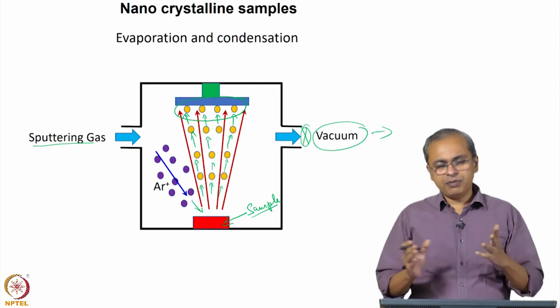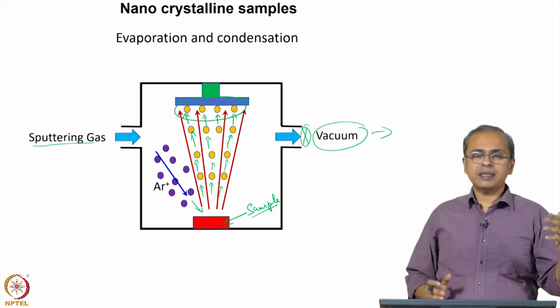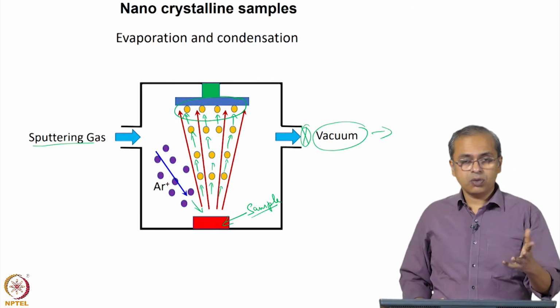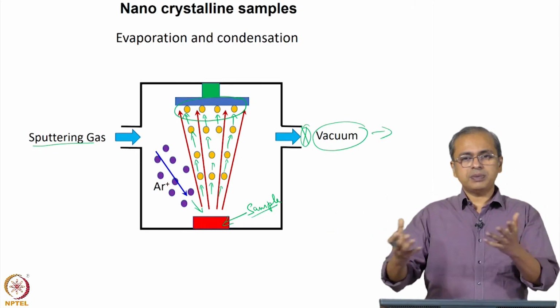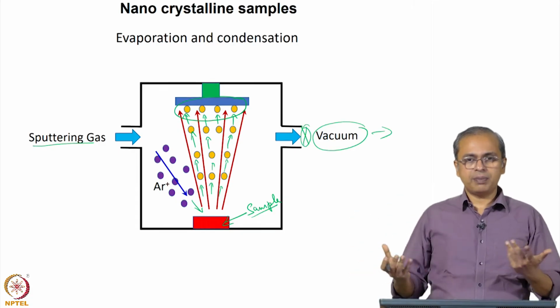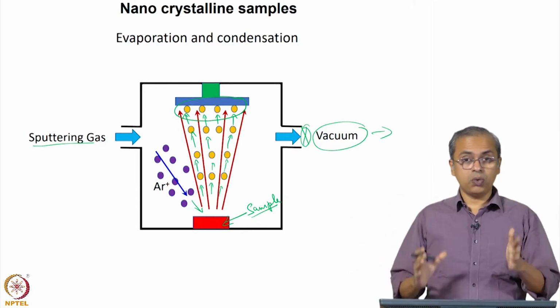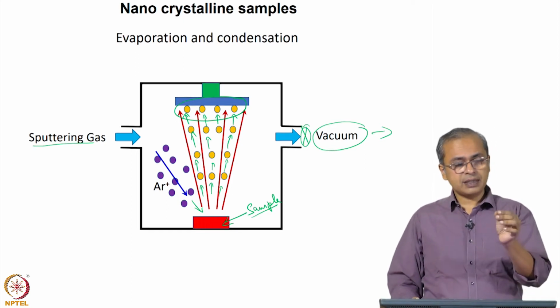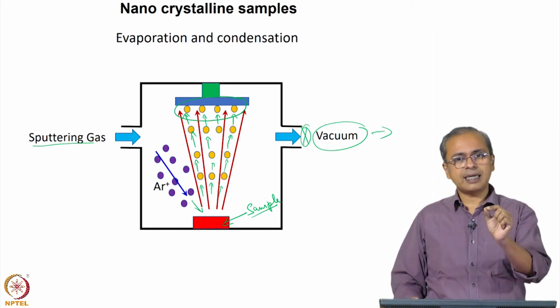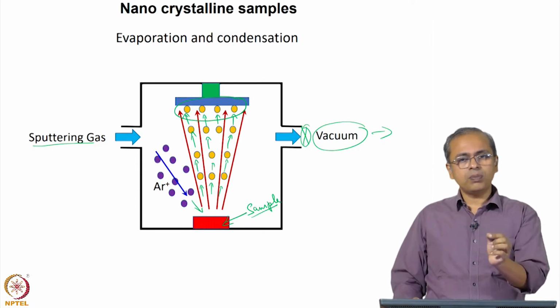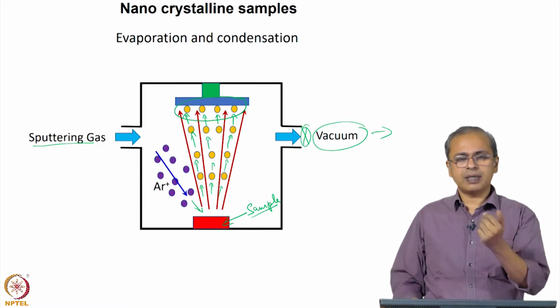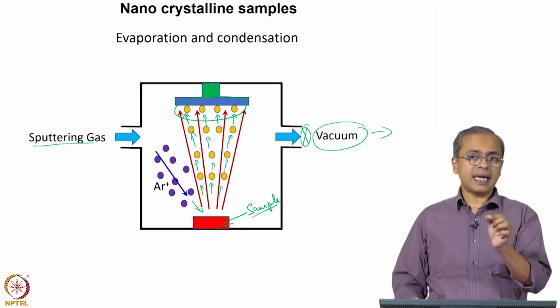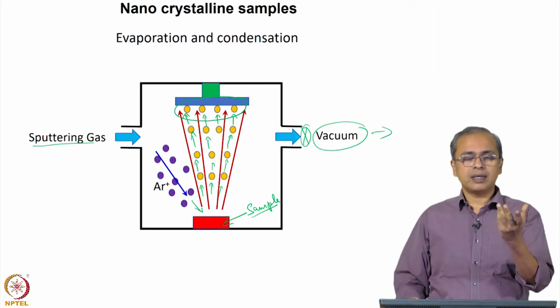In these three, relatively speaking, the thermal evaporation process is very fast. Normally your vacuum chamber may take half an hour or 45 minutes or even an hour to reach the low vacuum that you are interested in. Once you reach that low vacuum, in the thermal evaporation process, you start raising the current gradually, so that you do not have non-uniform heating.